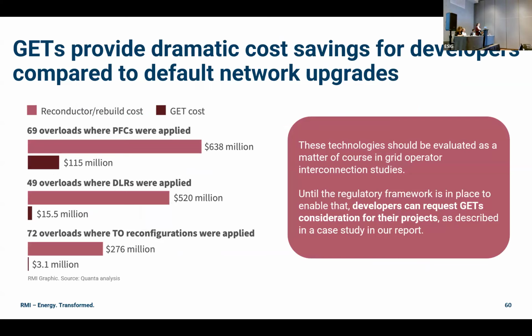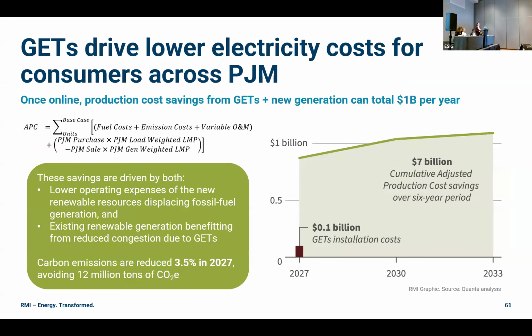So we did a cost comparison for each of those cases where power flow controllers or dynamic line ratings or topology optimization were applied. And the savings for developers are really, really large. Not only that, but to pivot to the production cost savings a little bit, the savings for consumers are also very large. So we found that once online, the production cost savings as formulated here in PJM from grid enhancing technologies and the new generation that they enabled could total $1 billion per year in savings, compared to a $0.1 billion or $100 million cost to install these 95 grid enhancing technologies.